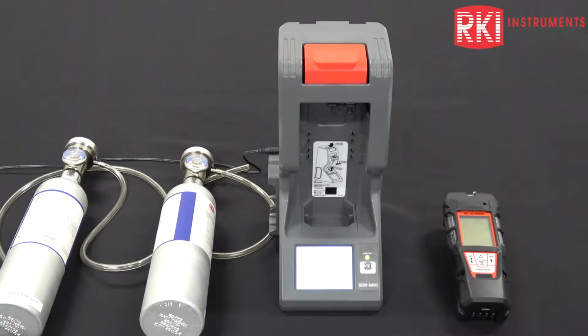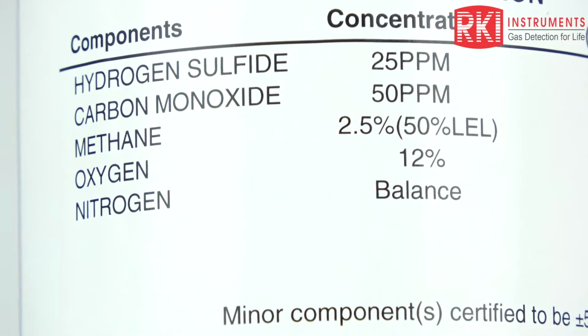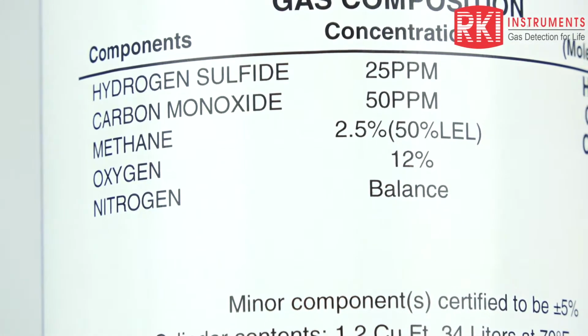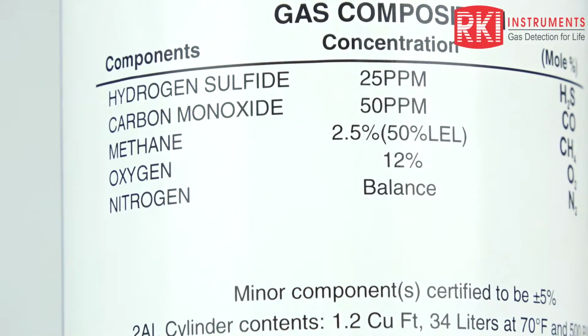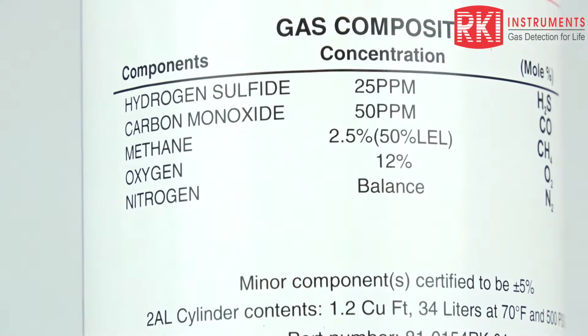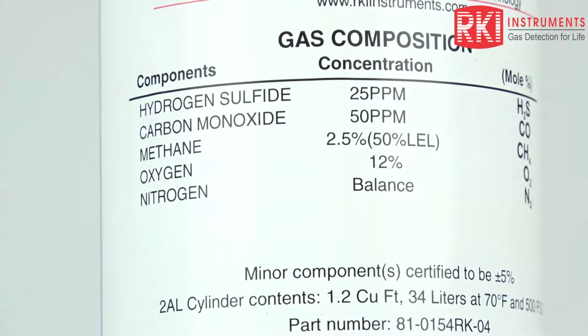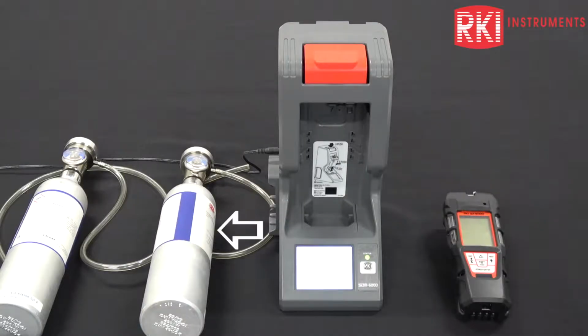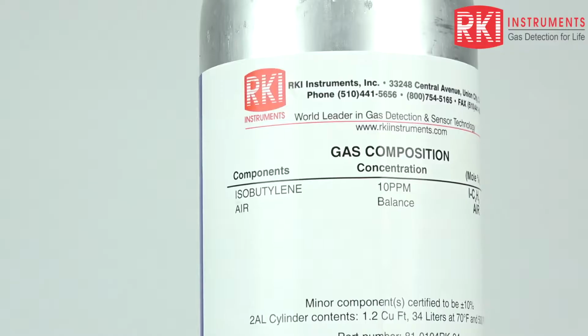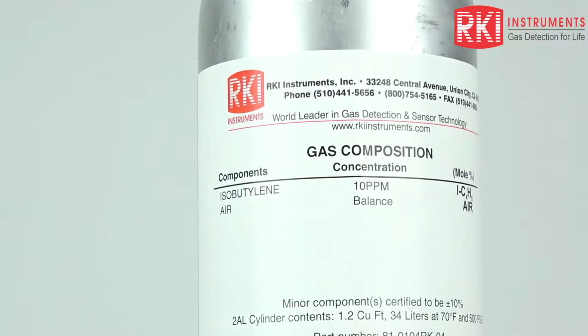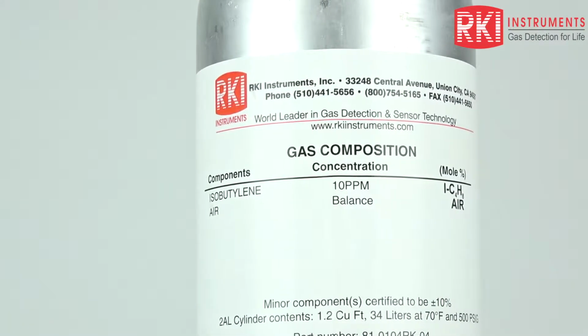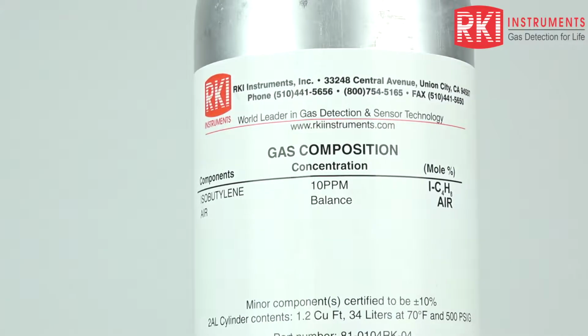Towards the left side on the cylinders, the very left side is a 4-gas mix cylinder. Concentrations are 25 parts per million of H2S, 50 ppm CO, 50% LEL methane, 12% oxygen in nitrogen balance. And over to the right of it is a 10 parts per million isobutylene cylinder. That is for the PID sensor, 0 to 50 parts per million.